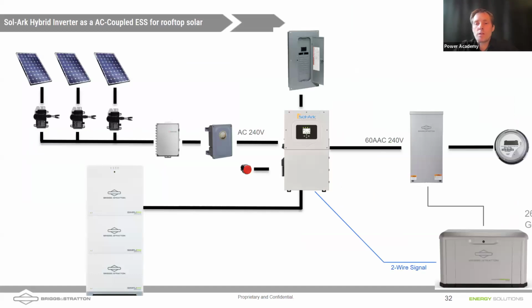Here's another example where we're going to show you how to program in for AC coupled solar. So we're showing an example that also includes a generator here with a transfer switch. Now that's only one example. If the grid goes down in this scenario, what we would have is the batteries, and solar covering the loads, until the battery power gets low. If the battery power gets below the threshold that we set earlier for generator charging, then that generator would get a 2-wire signal to start. It would start up, the transfer switch would switch over, and now I'd have flow of power out of the generator into the batteries and into the loads for the house.